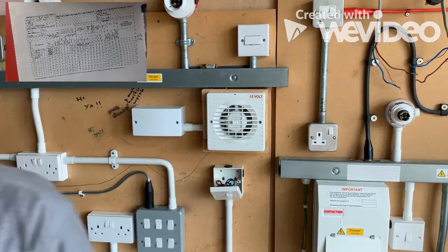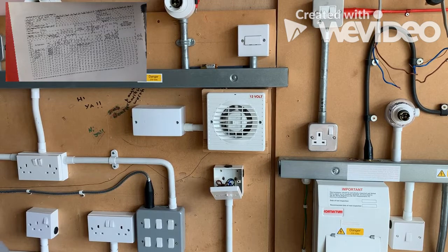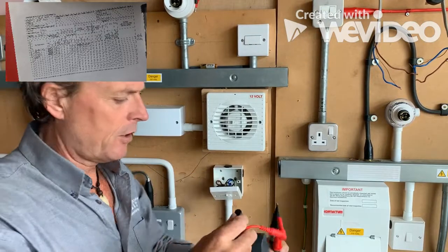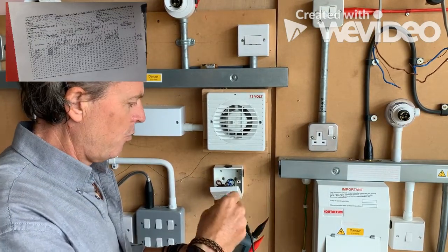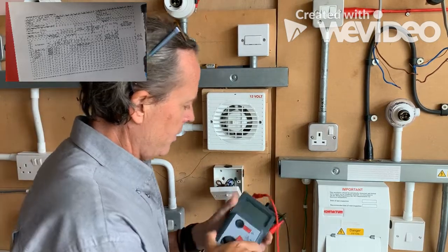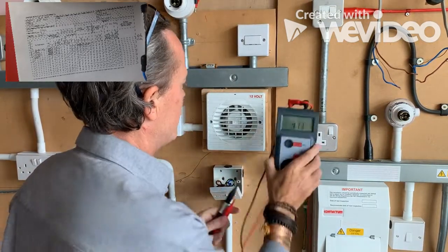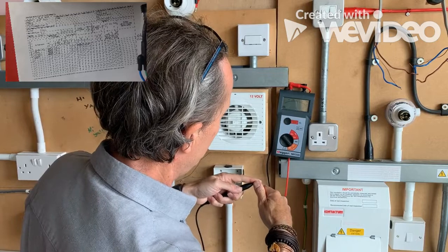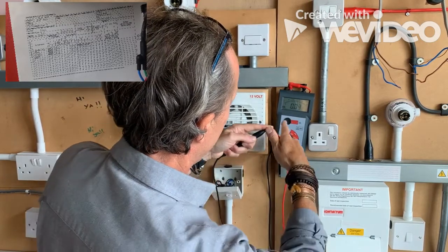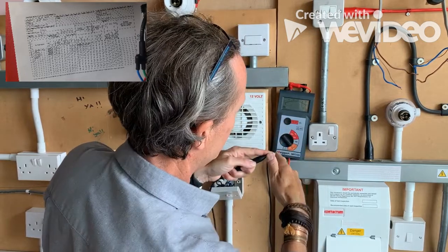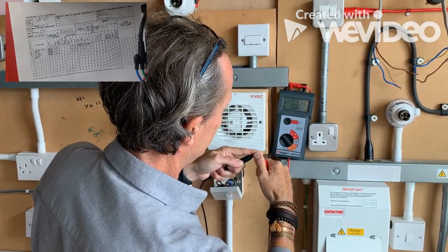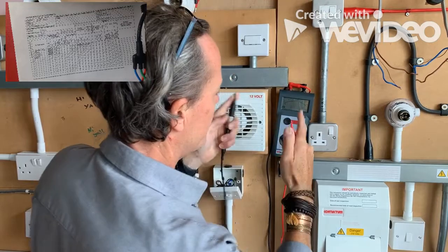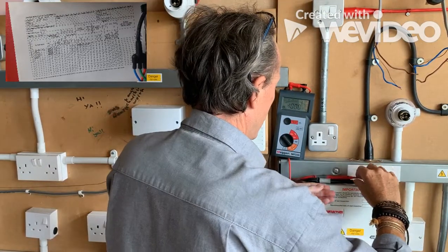So this is the end of our shower circuit here. We're going to get our tester, put the tips on, and connect the tester together. Then we're just going to make sure that we null our leads — hopefully you can see that. We press the test button and we can see with quite a bit of force there that we've got zeros. So we've nulled our leads.